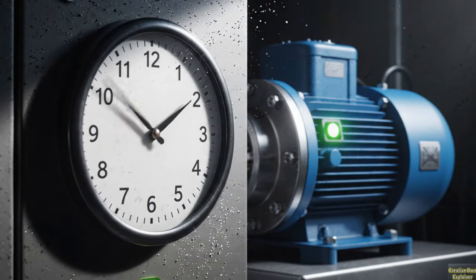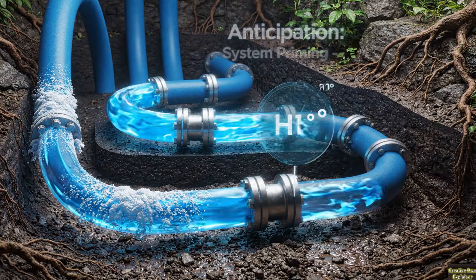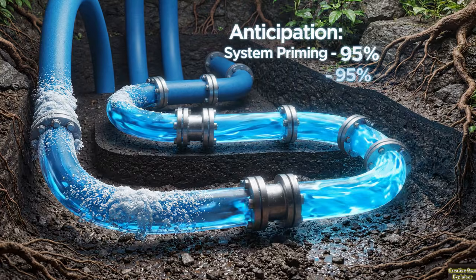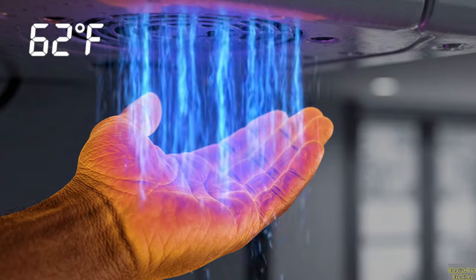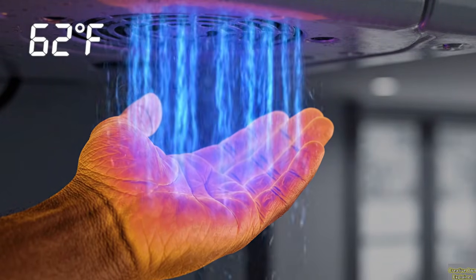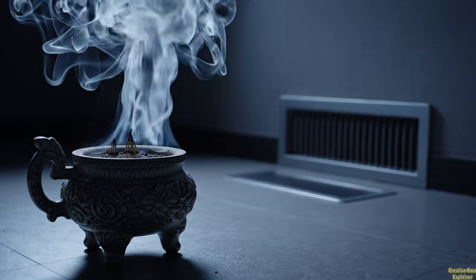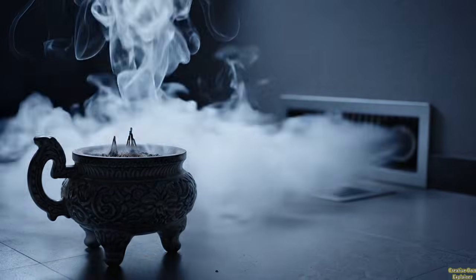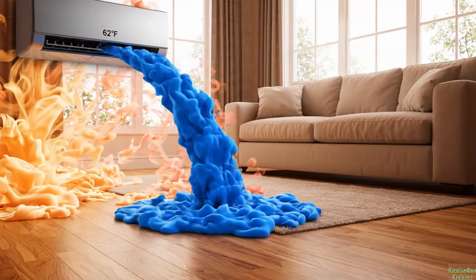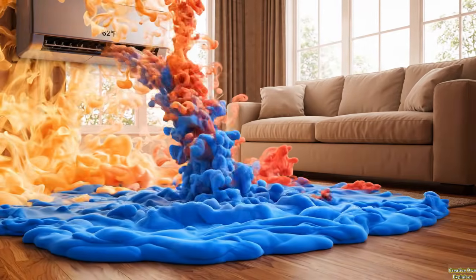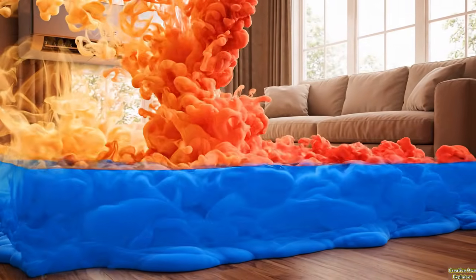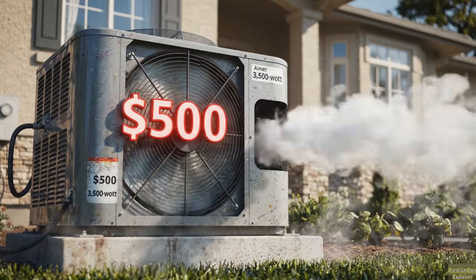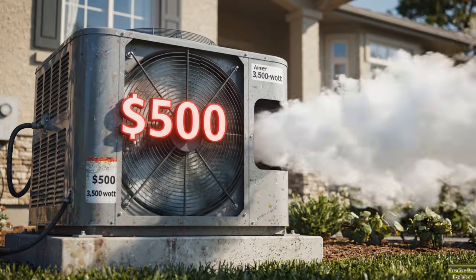Wait 15 to 20 minutes for the water to complete its first full circuit through the buried coil. Hold your hand in front of the fan. The air coming through should be between 60 and 65 degrees Fahrenheit. If you want the full experience, hold a stick of incense in front of the unit and watch the smoke flatten sideways and stream horizontally across the room. That is cold, dense air displacing the warm air above it. That is the earth doing the work that a 3,500-watt machine has been charging you $500 a summer to do.